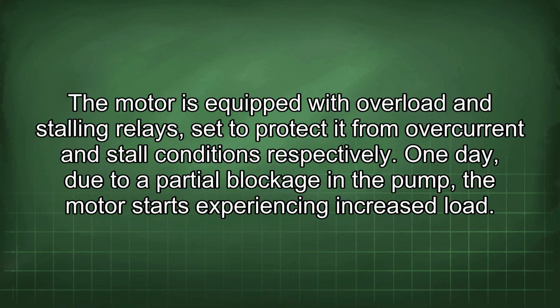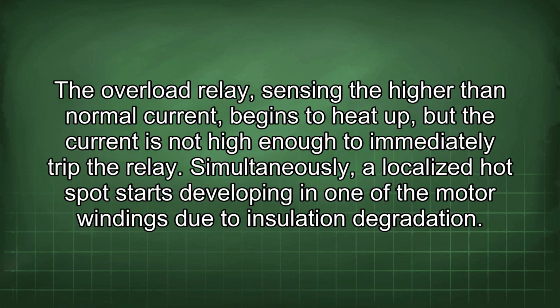The motor is equipped with overload and stalling relays set to protect it from overcurrent and stall conditions respectively. One day, due to a partial blockage in the pump, the motor starts experiencing increased load. The overload relay, sensing the higher than normal current, begins to heat up, but the current is not high enough to immediately trip the relay.